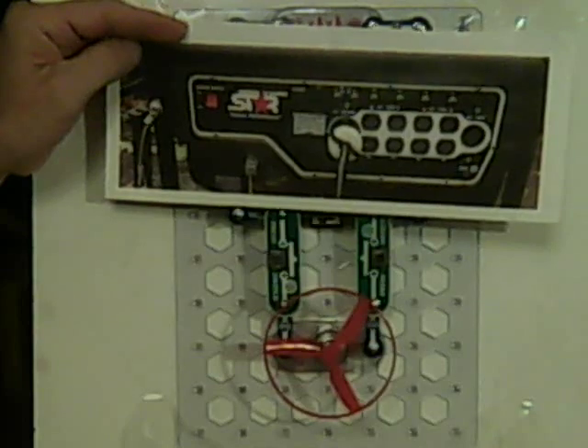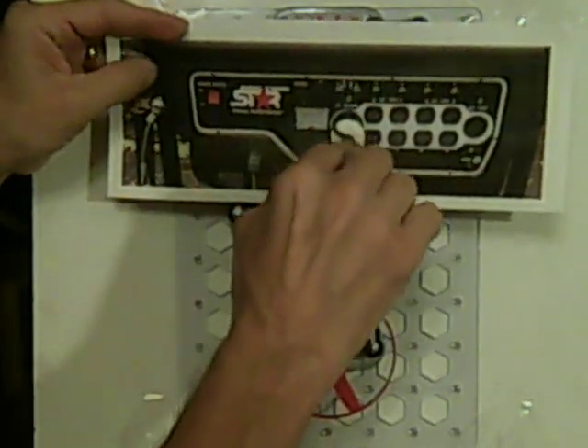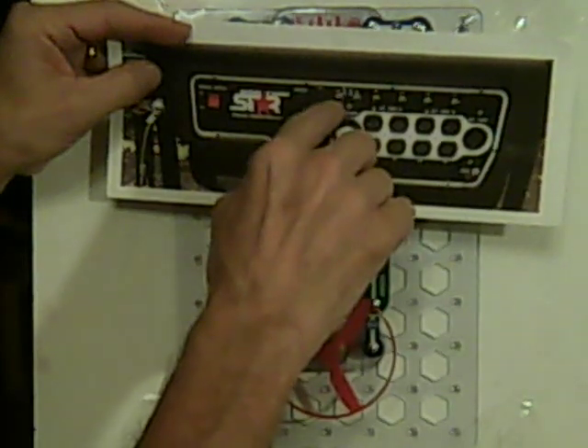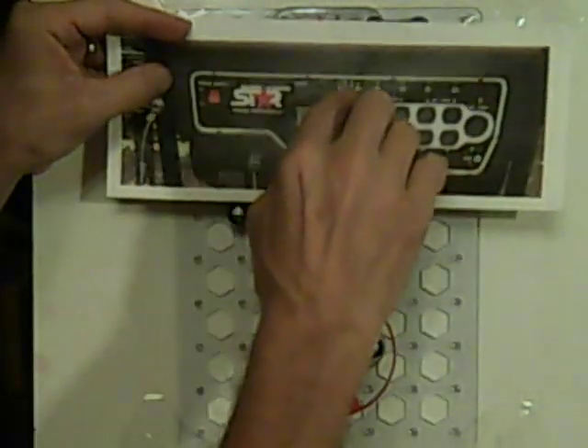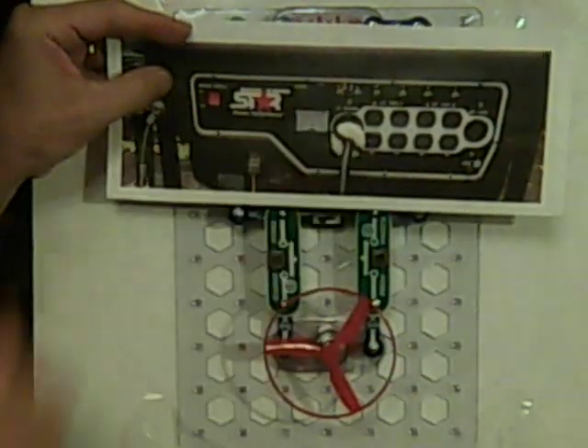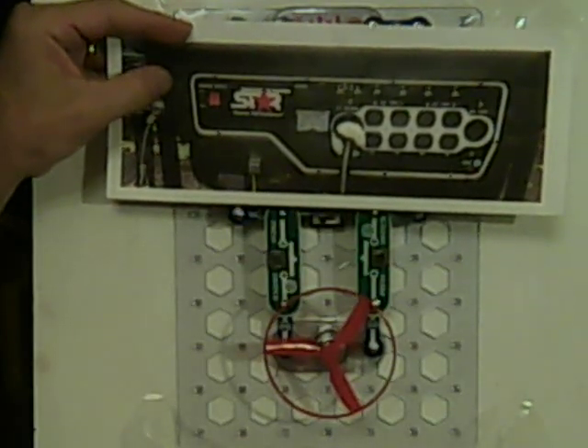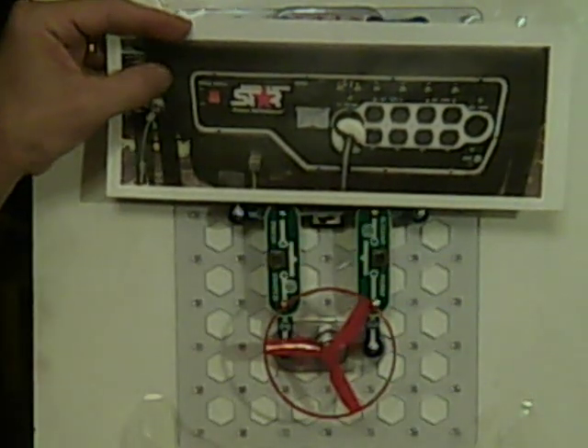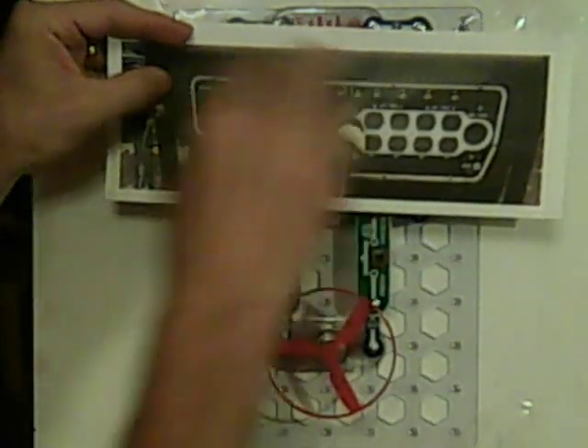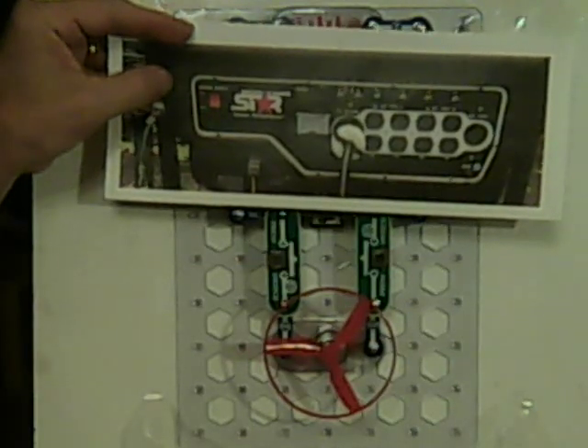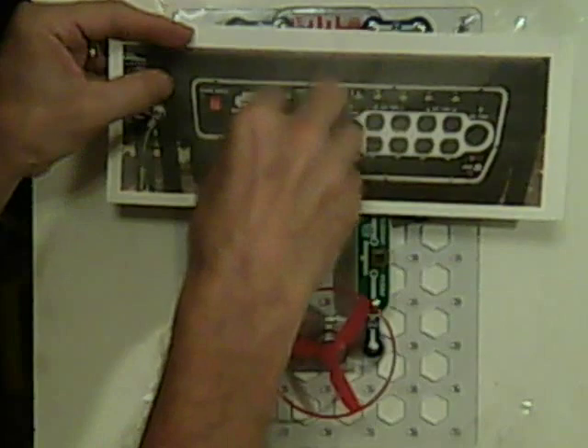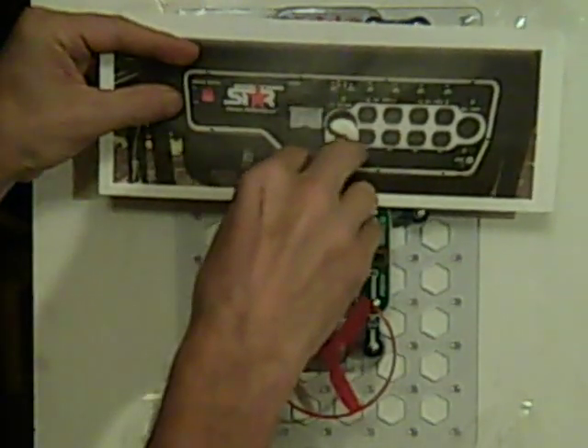This is a picture of the front panel of the generator. In order to power the grinder pump, they were using the four-wire 240 volt output from the generator. That outlet is protected by two circuit breakers - these are reset only push button reset circuit breakers - and it also has a voltmeter on the front panel to show the voltage it's running at. When they were running their grinder pump off this generator, there was a failure in the grinder pump and they were accused of having set up the generator incorrectly to run at 120 volts instead of 240 volts. It only takes a brief familiarity with this generator to realize it's not possible to set this generator up at 120 volt operation on the four-wire output.